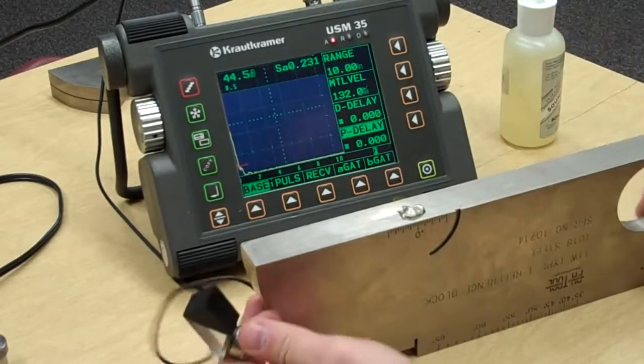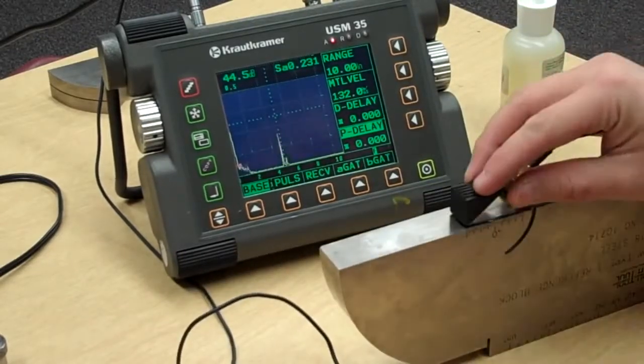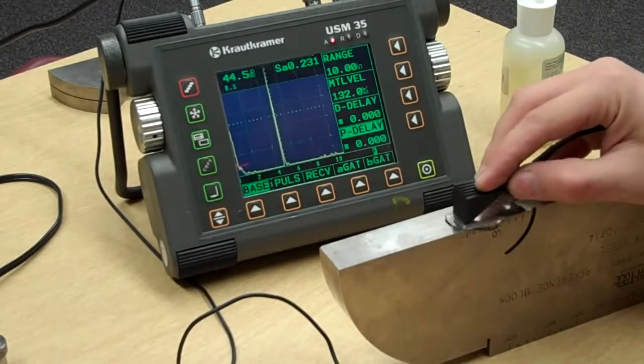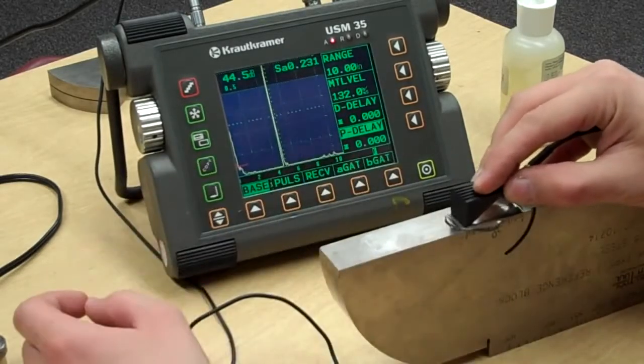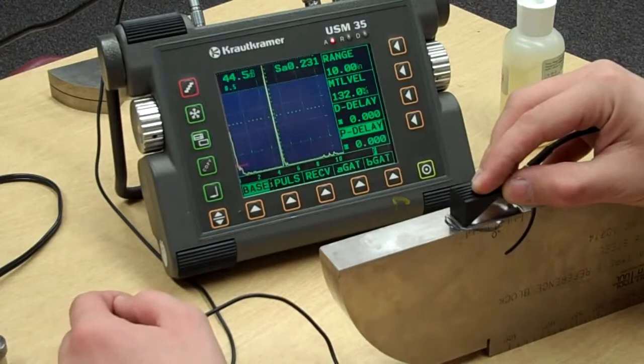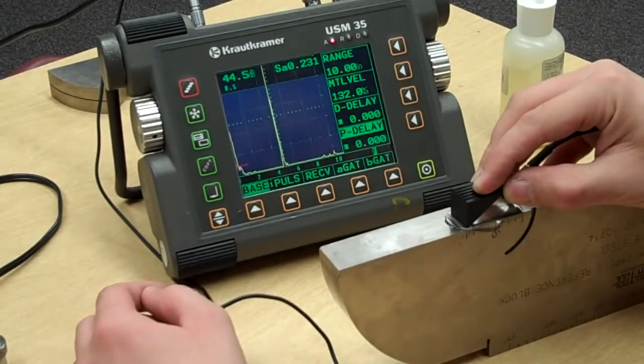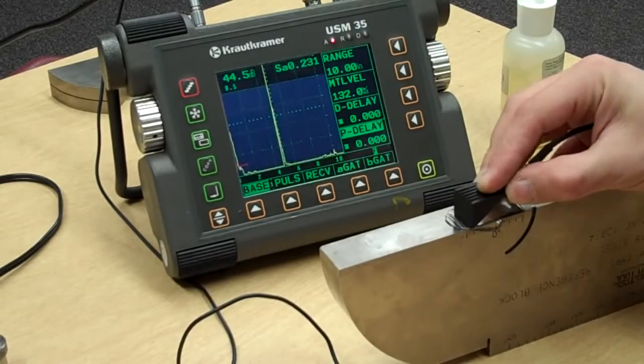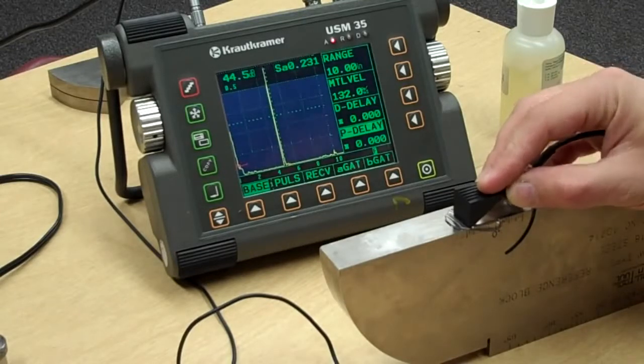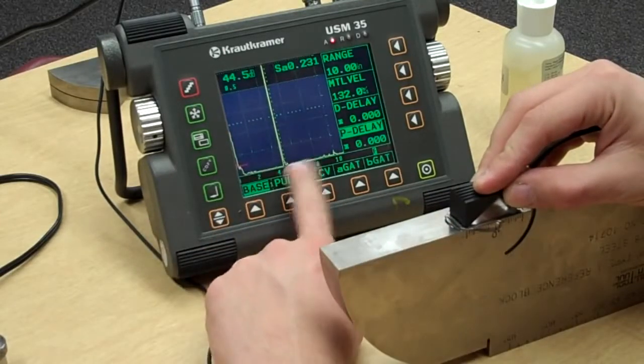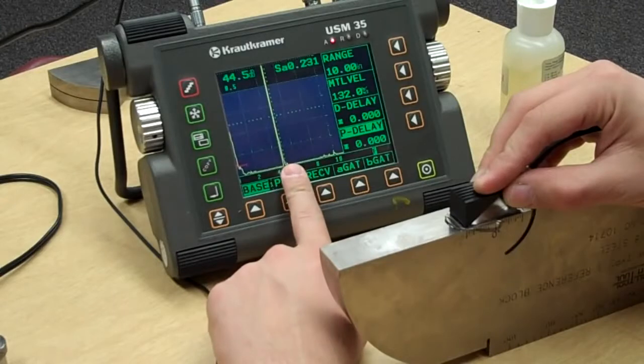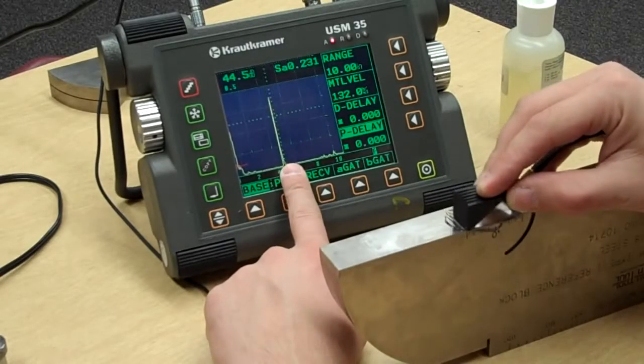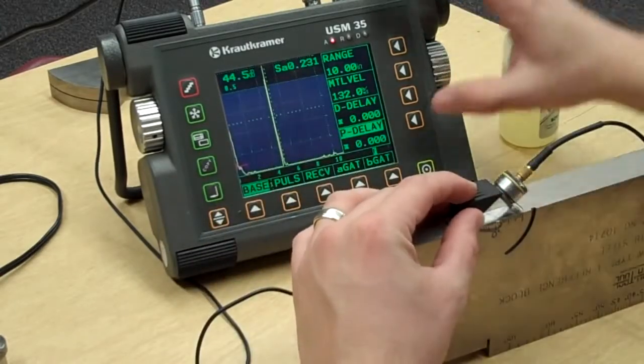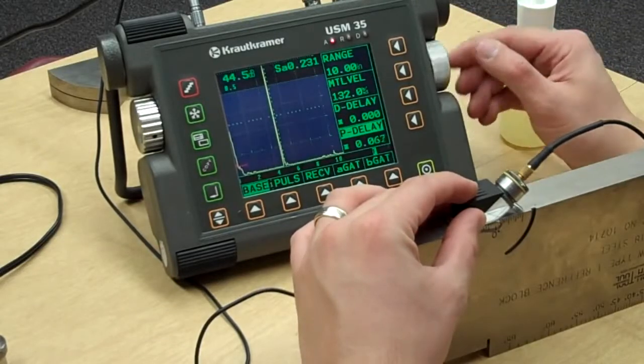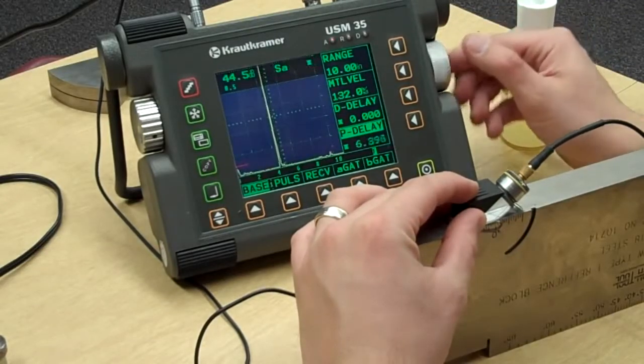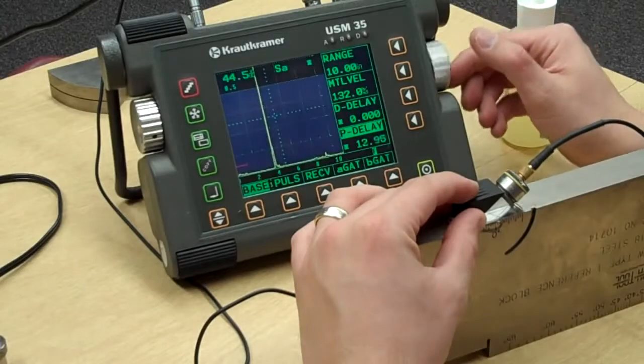Alright, so just distance is all we're doing right now. Just basic shear wave distance. We don't really need to do anything for complete calibration yet because we're not ready for that yet. You just need to see the distance stuff. So, just taking a gander here, I parked my transducer right over the 0. Got a signal here and a signal over here. Well, I know I need that signal at 4 inches, so I'm going to take my delay and push that signal over somewhere near 4 inches.